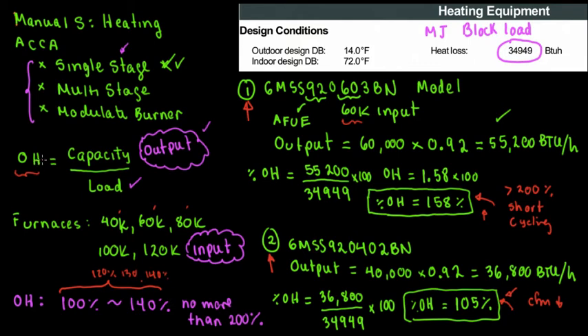One more thing about this. Because option number two is smaller, it's a 40K furnace, the CFM also is lower. When it is bigger, the CFM also is bigger. Manual S indicates size your furnace for single stage within 100% to 140%, that's the optimal. Personally, I don't go 100 or 102%. I would go after 110, maybe 120%, 140%, yes. If you don't comply with the CFM requirement of your house, you can always go past 140 to the range of 140 to 200, but no more than 200.